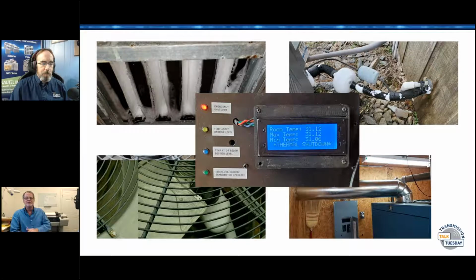If you look to the top right there, you'll see the nice big ice ball that built up on the Freon line. And in that bottom left photo you can see the entire compressor was frozen up. So when the photo in the center was taken, I had just hooked that thing up, hung the temperature probe, and you could see it was well above the alarm and shutdown range.